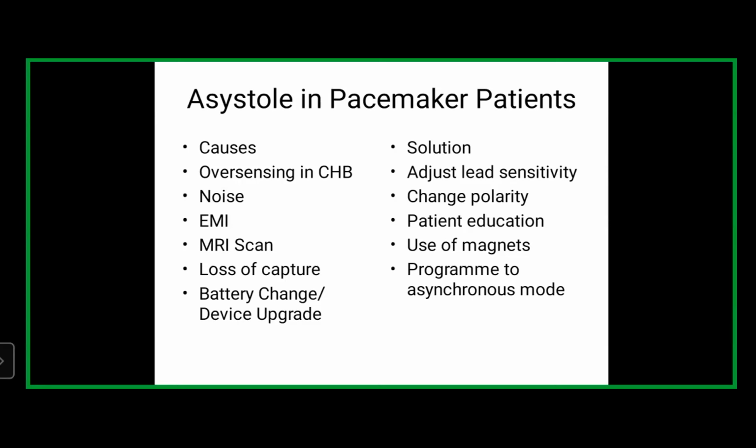Then battery change, device upgrade, that's another point. Although the risk of infection increases with use of temporary pacing, it depends anyway. While doing a battery change, as a physiologist, you want to keep your eyes on the ECG to look out for asystole, especially for dependent patients, whether it's CRT or pacemakers.